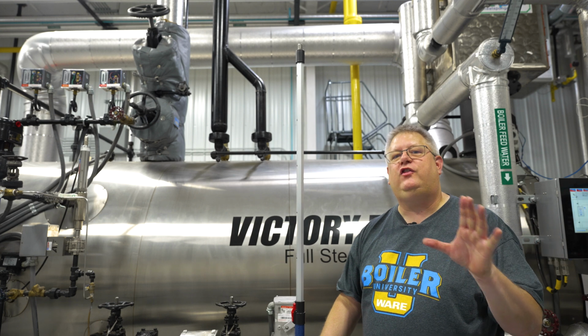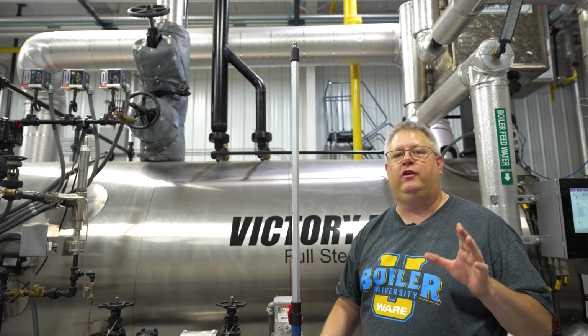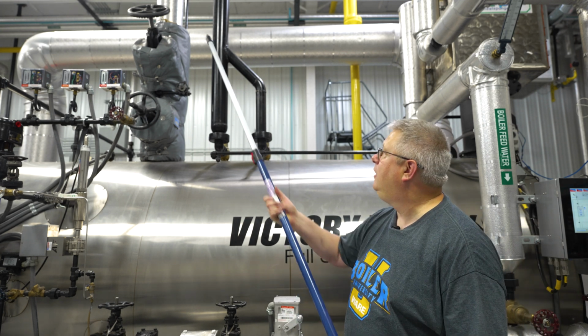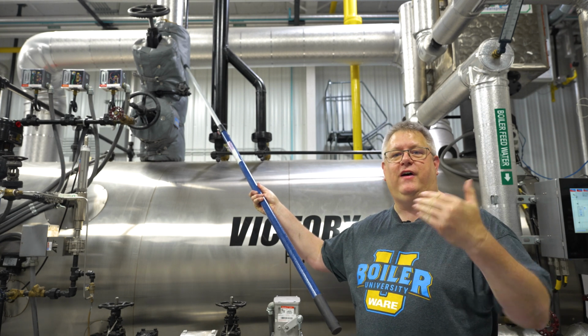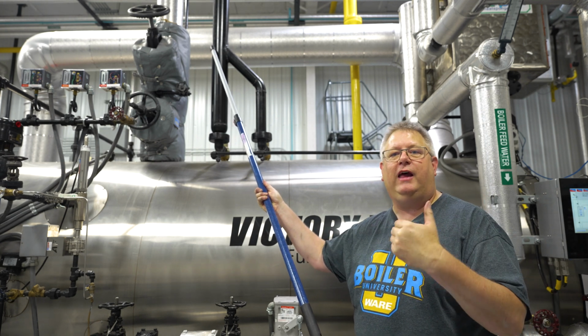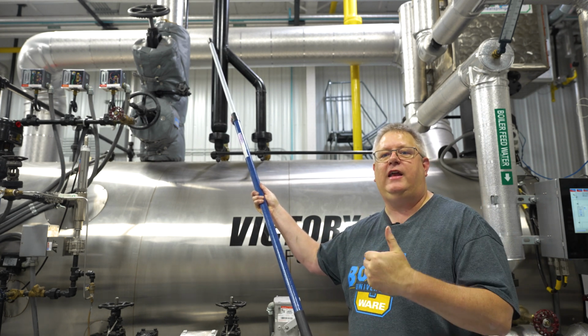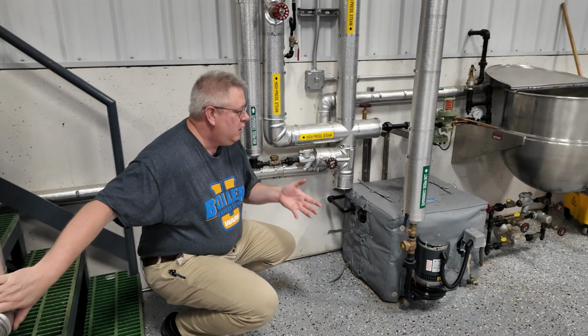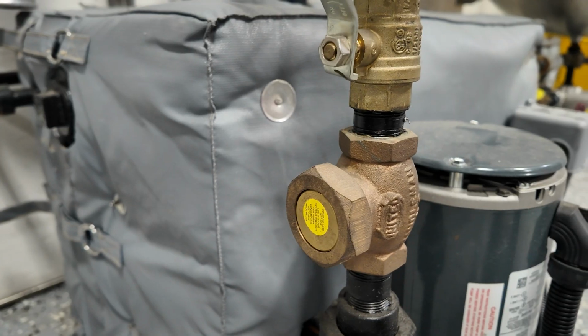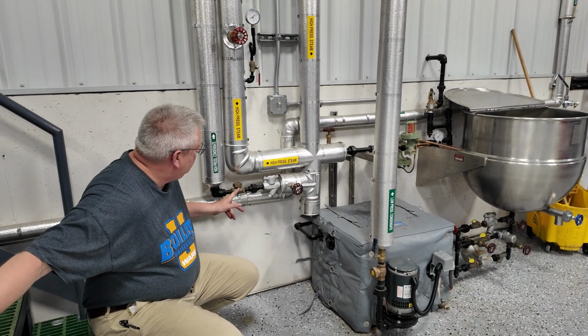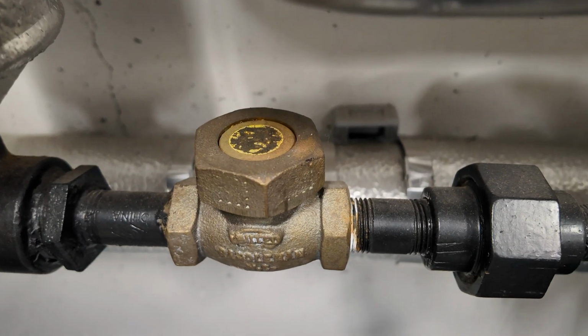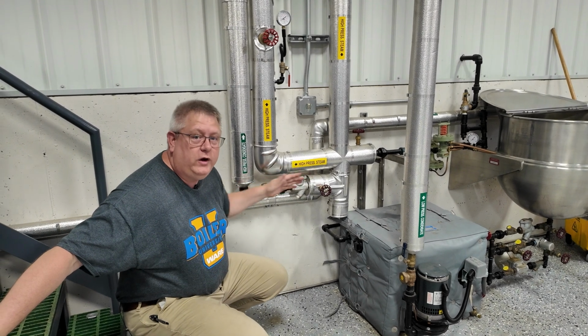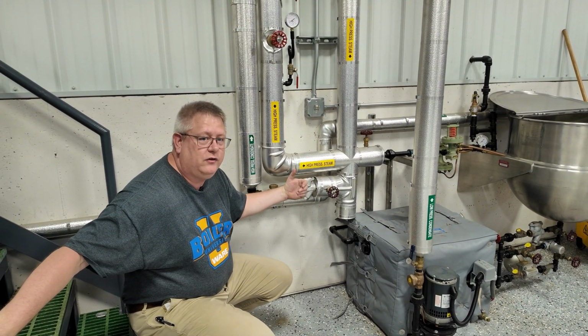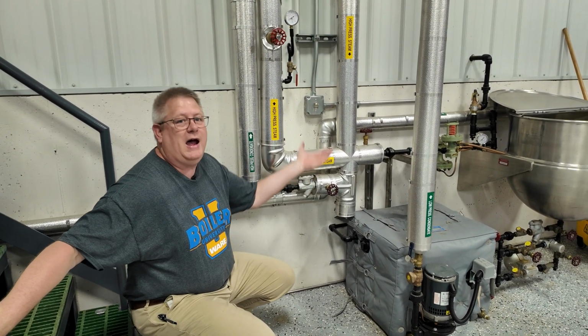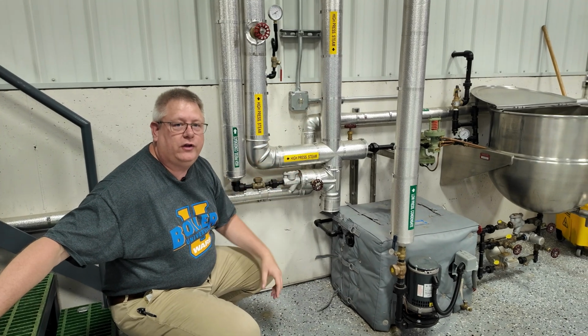Probably the biggest check valve in your boiler room is the non-return valve on the boiler. This check valve prevents pressure from other boilers entering this boiler when this boiler is shut down. Here's a couple more. We've got one on the outlet of a pump. Just about every pump's going to have a check valve on the outlet of it. And here's another one on the outlet of a steam trap. If we shut the system down, we don't want all the condensate in the condensate return system to be sucked back into the steam system by the resulting vacuum.